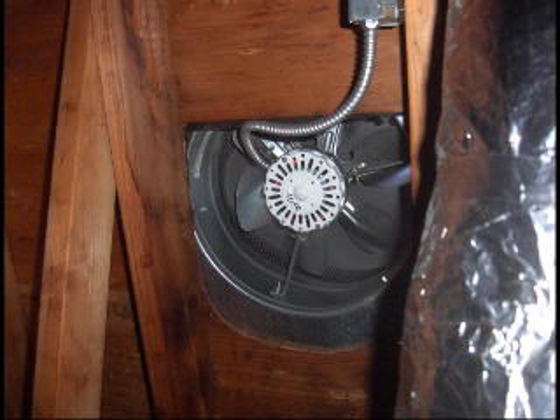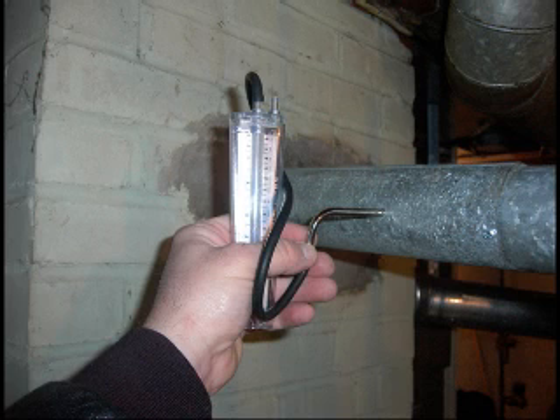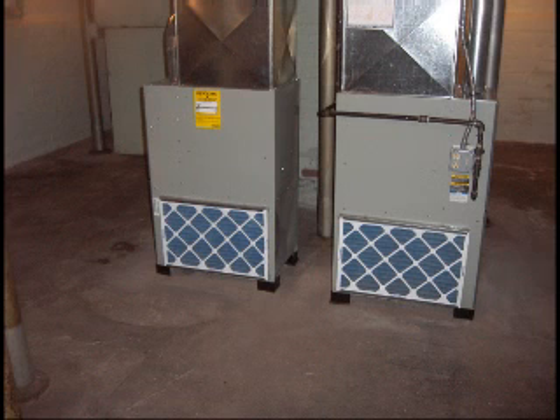When I'm talking about high draft, I'm talking about air getting sucked up the chimney. And so you can have a high stack effect. You can have pressure problems in the basement, depressurization, pressurization. You can have fans in houses. You can close doors and not have enough air. Regardless of the problem, there's too much air getting sucked up that chimney. And so then the water heater can't compete with it, and then it spills back down.